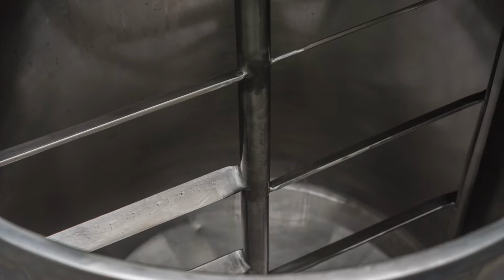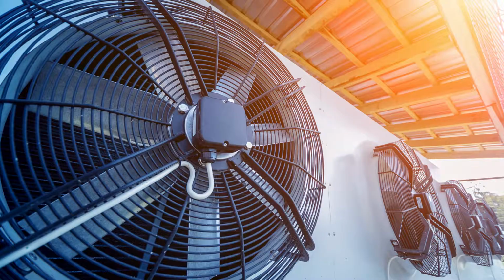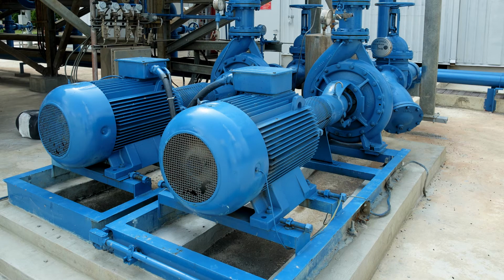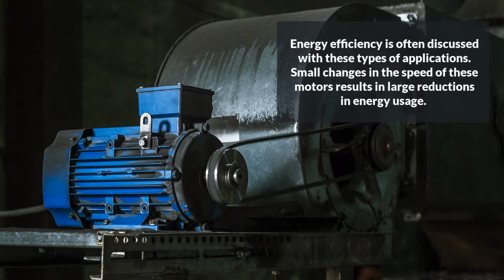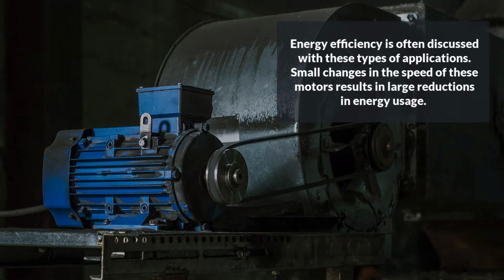There are also variable horsepower and torque applications, such as mixers or agitators, fans, and centrifugal pumps. These are the type of applications where energy efficiency is often discussed. Small changes in the speed of these motors results in large reductions in energy usage.